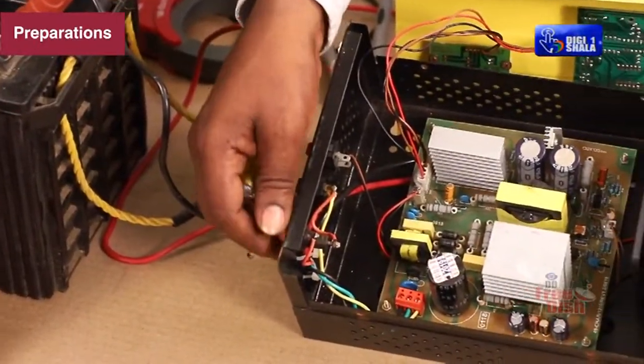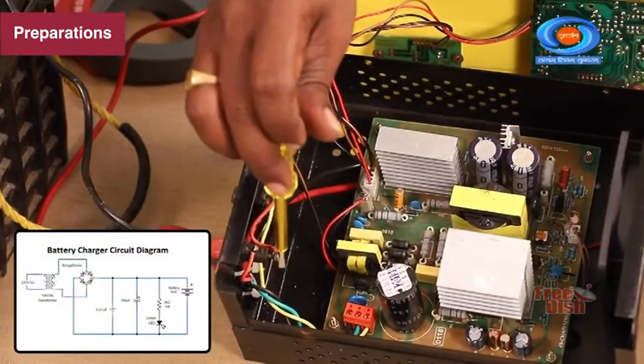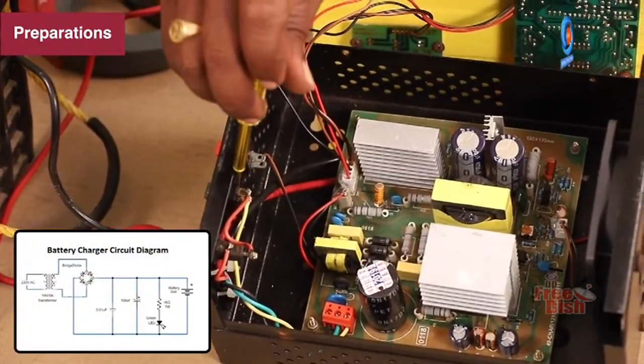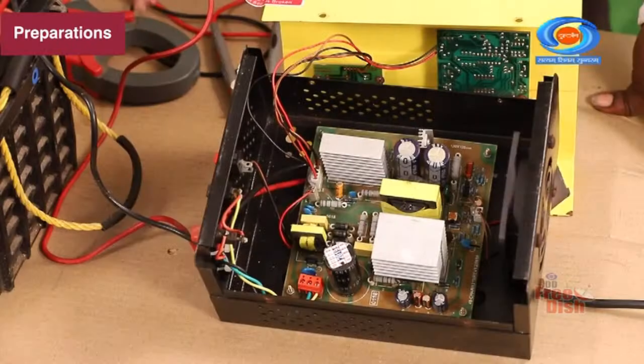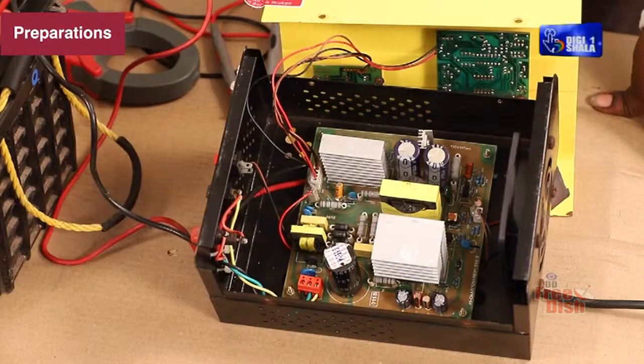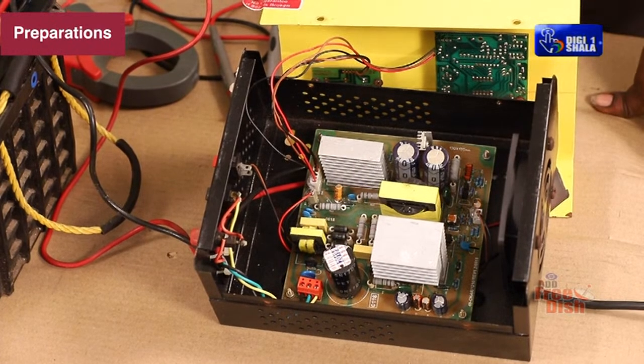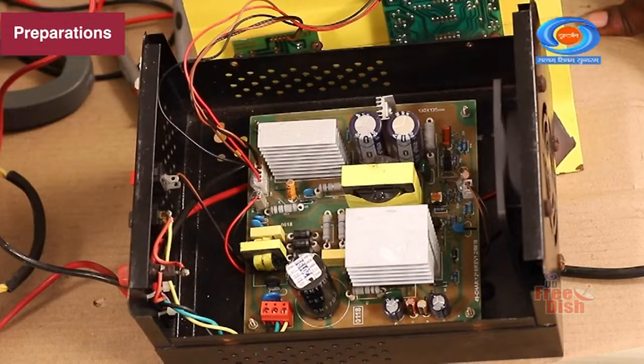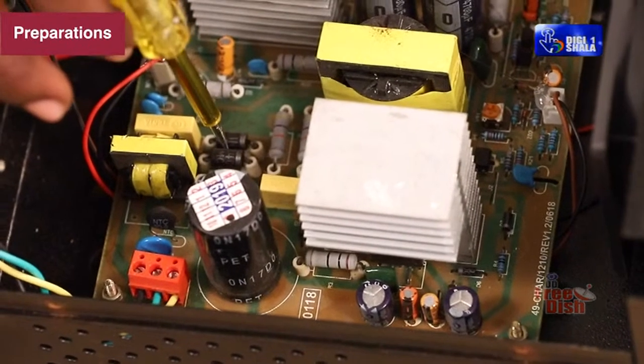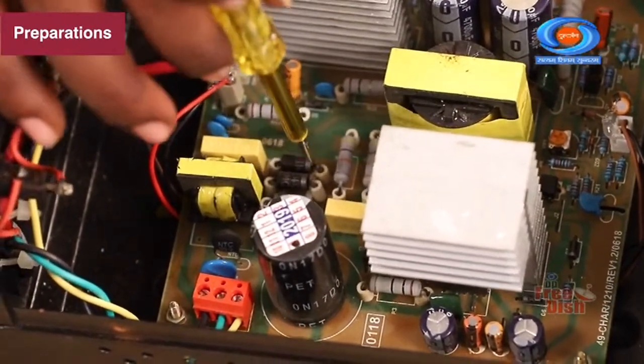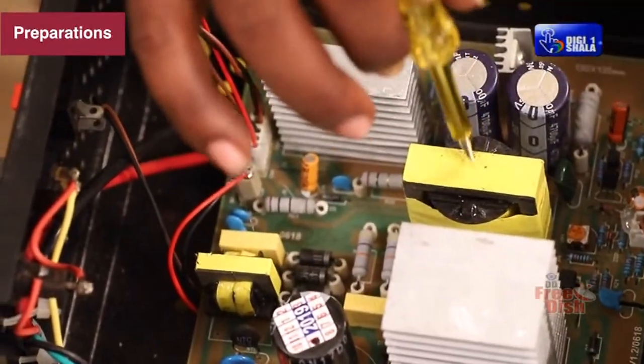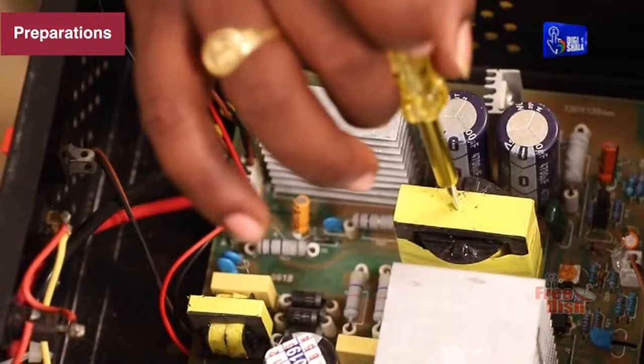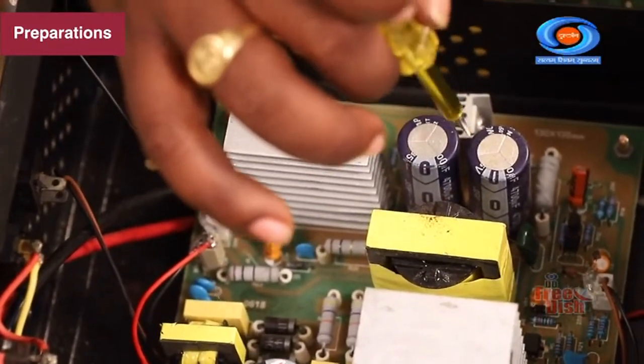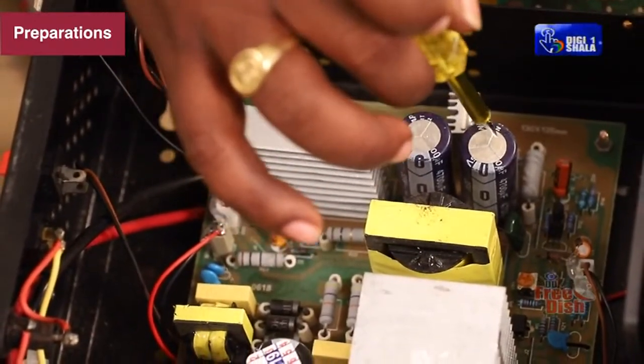Trace the battery charger circuit as shown. Check the circuit for an availability of charging voltage at battery connecting terminals. If the voltage is not available, check the fuse provided in the fuse carrier. Test the voltage output at the bridge rectifier output with a multimeter. Check the conditions of bridge rectifier diodes. If found defective, replace them. If all the diodes are okay, check the AC input to the bridge network. Check the charging control circuit for normal working after the charging circuit is repaired. Check the auto cutoff of AC mains is off when the battery is fully charged. If auto cutoff is not functioning, check the diode connected to the potentiometer and voltage at relay terminals.